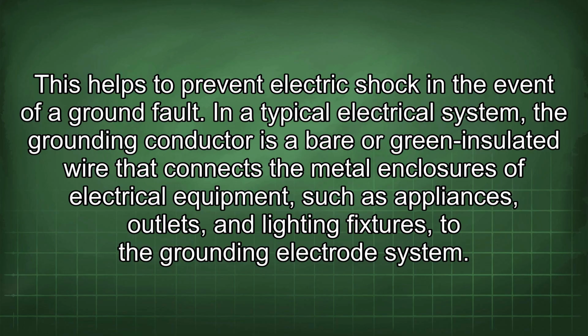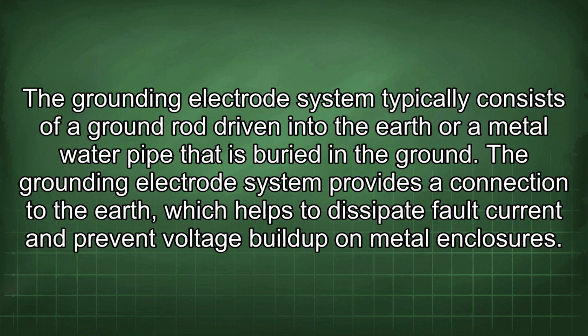In a typical electrical system, the grounding conductor is a bare or green insulated wire that connects the metal enclosures of electrical equipment such as appliances, outlets, and lighting fixtures to the grounding electrode system. The grounding electrode system typically consists of a ground rod driven into the earth or a metal water pipe that is buried in the ground.